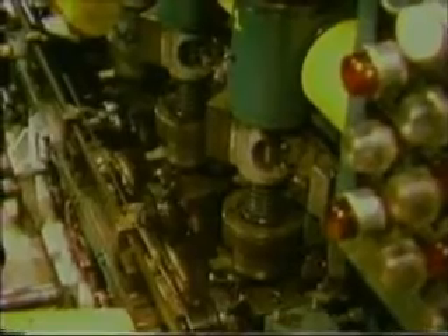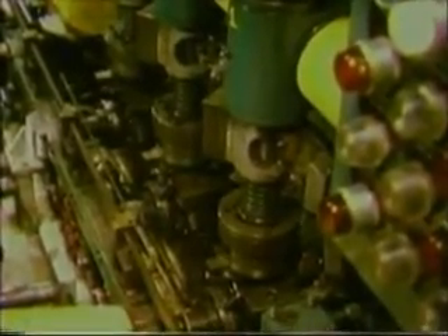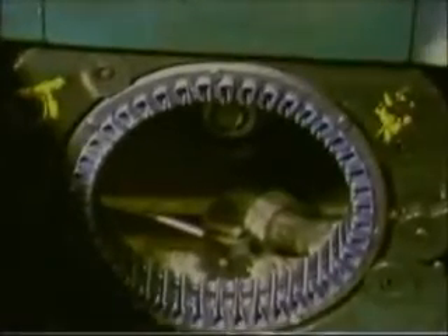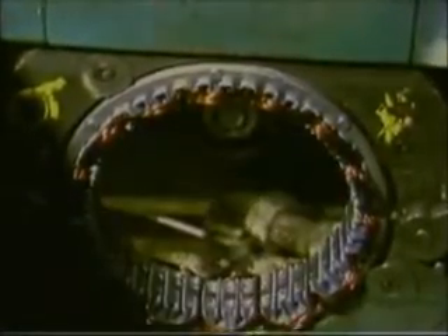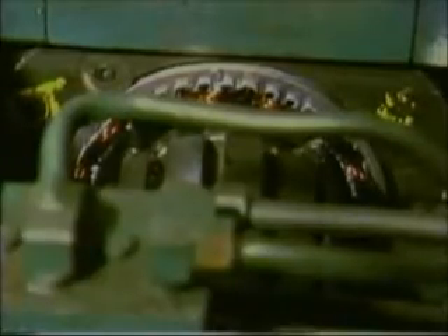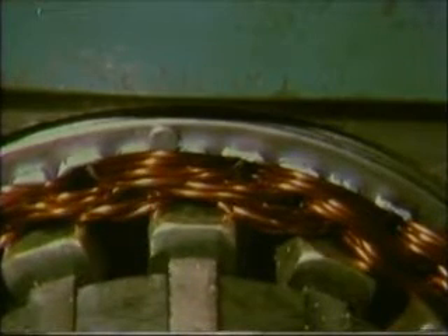The first layer of coils transfer to the stator core and are positioned in place. A forming press follows to achieve proper compacting. The second wind station performs exactly as the first, the only difference being the stator core lamination is rotated to a new position. Coils are stuffed and expanded into proper fit and placement. Again, the sequence for the third winder is such that coils are transferred from the winder and pressed into final position. Coil slots have been closed with rope and the coils are ready for varnish.